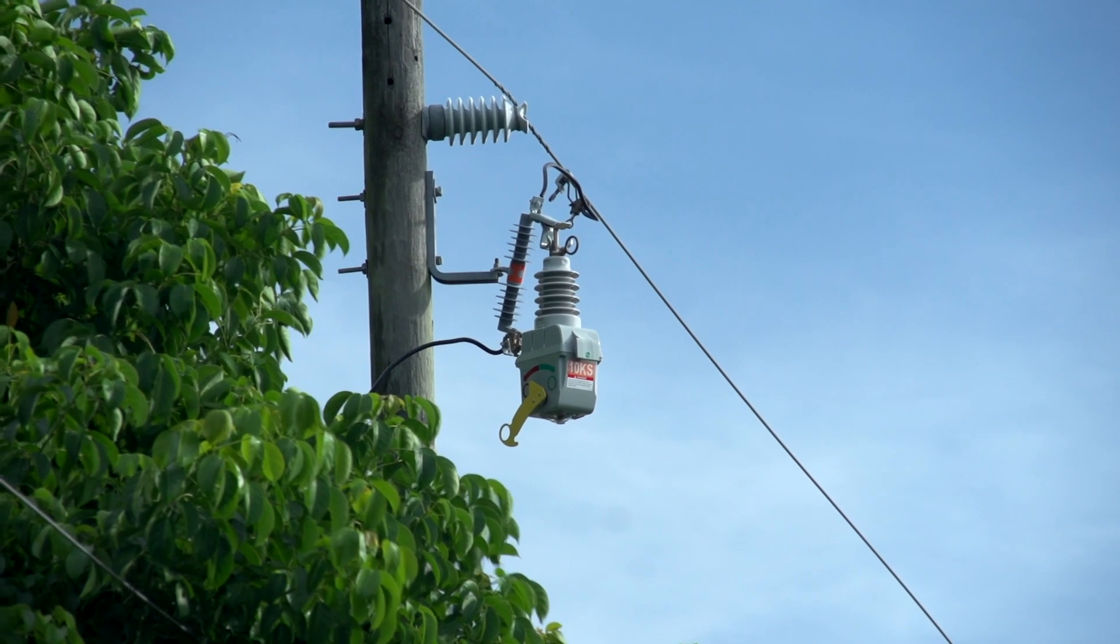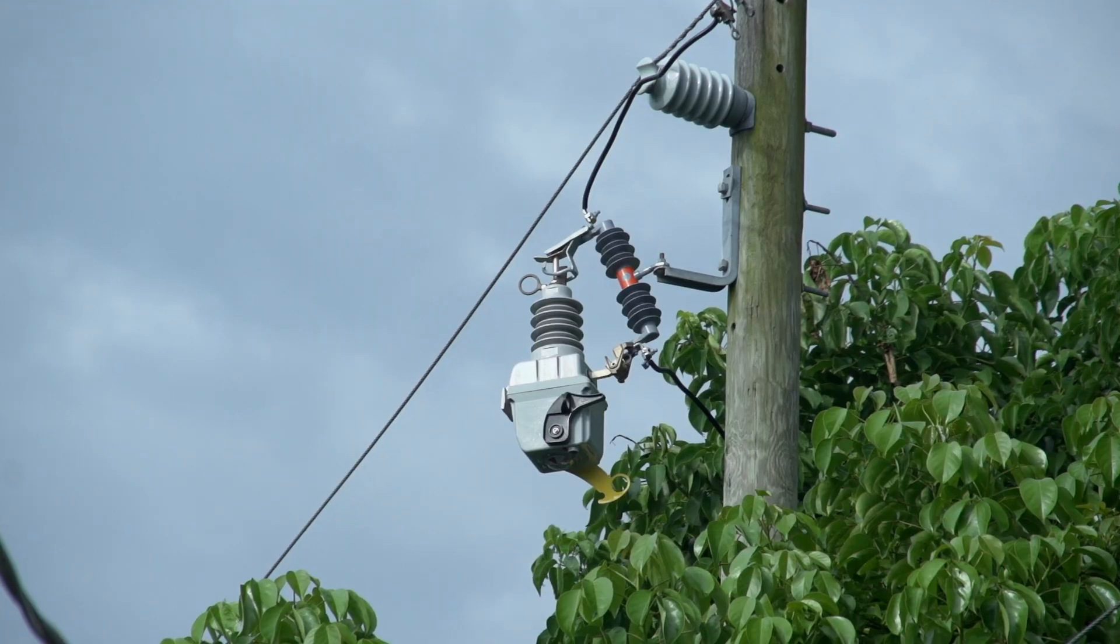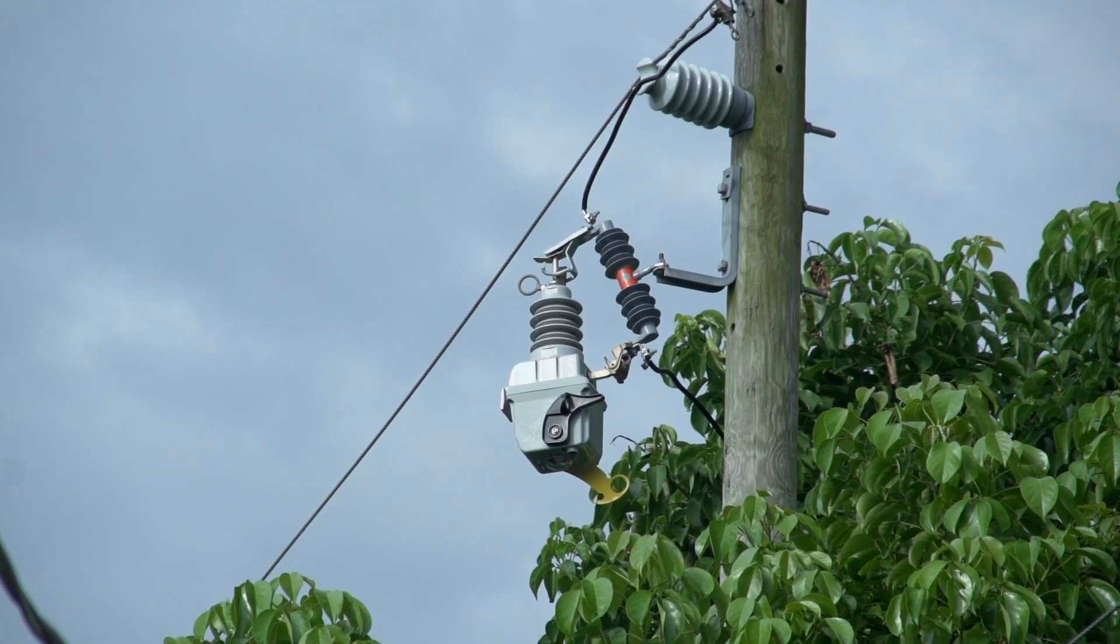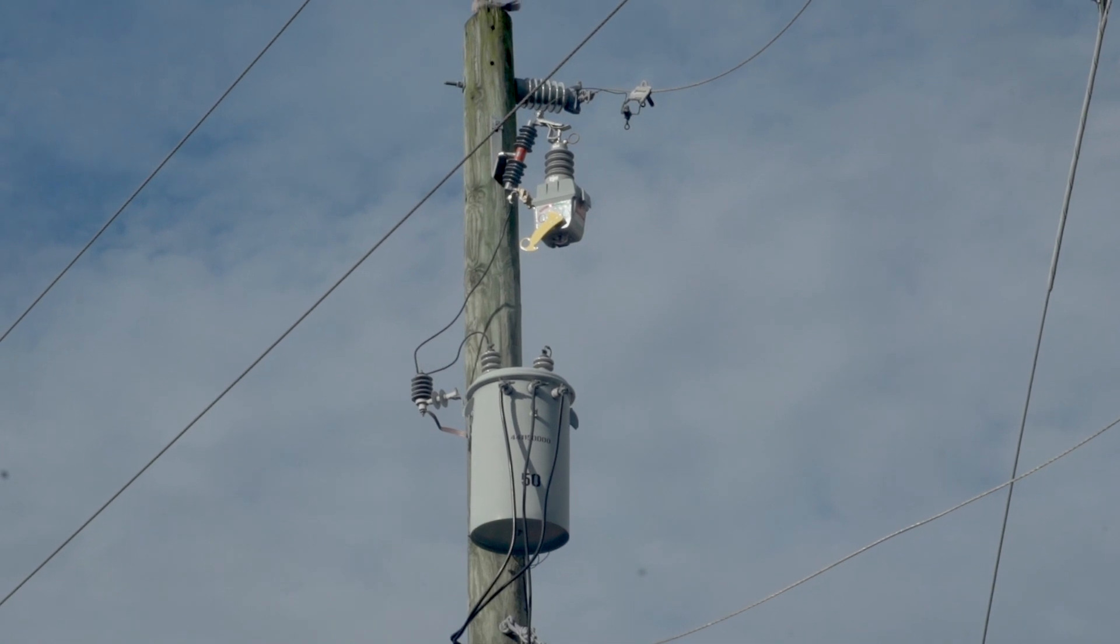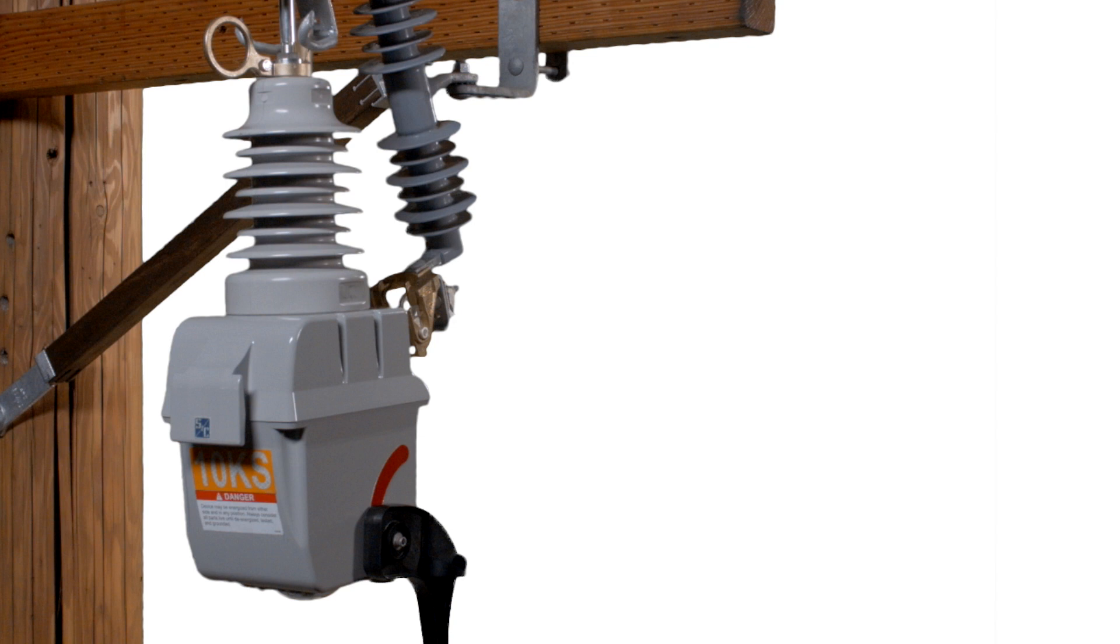The VacuFuse Self-Resetting Interrupter is a single-phase, cut-out-mounted interrupter used to eliminate unnecessary permanent outages at an overhead distribution transformer. The VacuFuse Self-Resetting Interrupter is ordered factory configured with a user-specified FuseLink TCC curve, open interval time and protection sequence reset time.